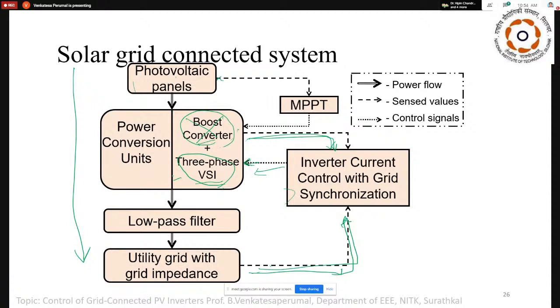It is 380 volt, so it is always pushed through the step-up transformer, from the 380 volt to the grid side 6.6 kV or 11 kV line. So central inverters always have the transformer connected between the inverter and the grid side. If the transformer is connected, the system reliability is very, very high in the case of a central inverter. Another inverter is called the string inverter.